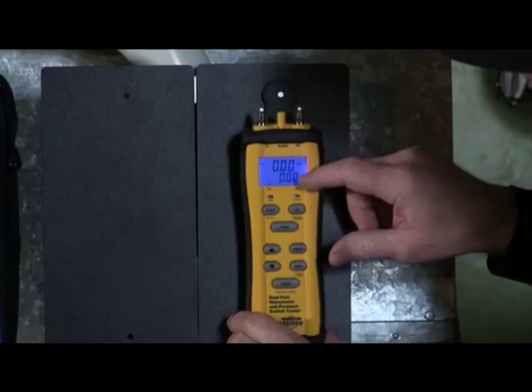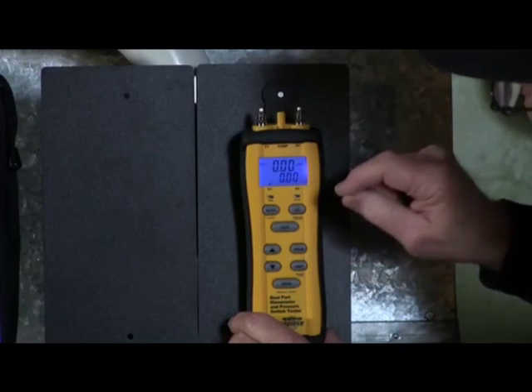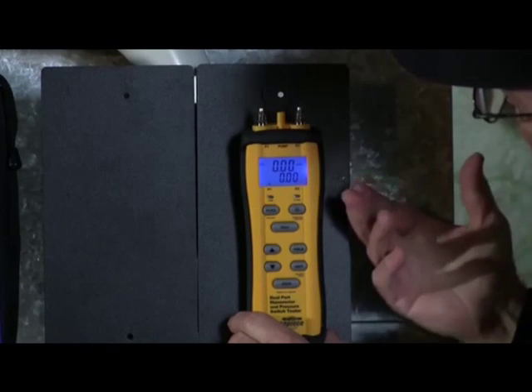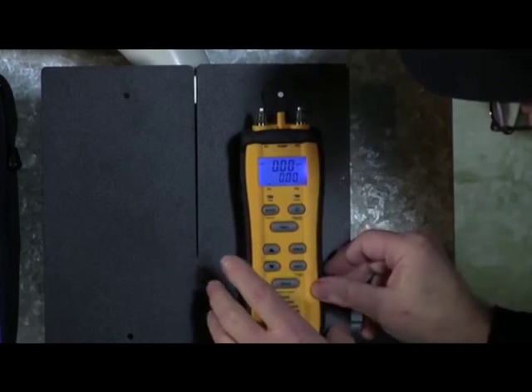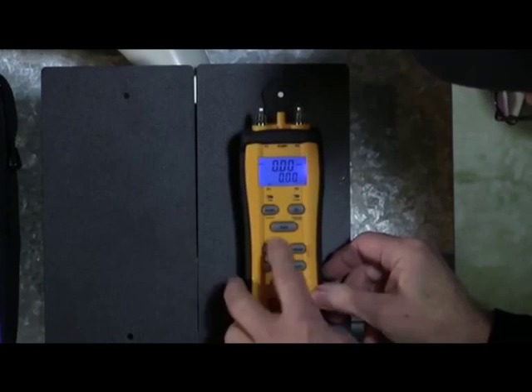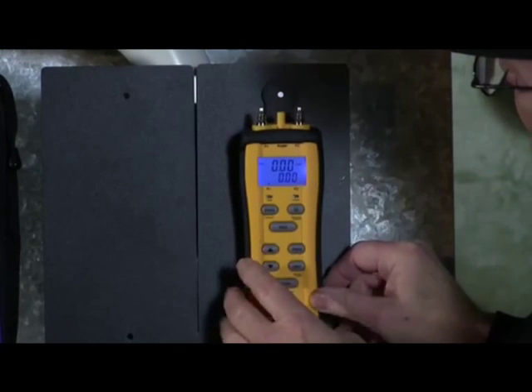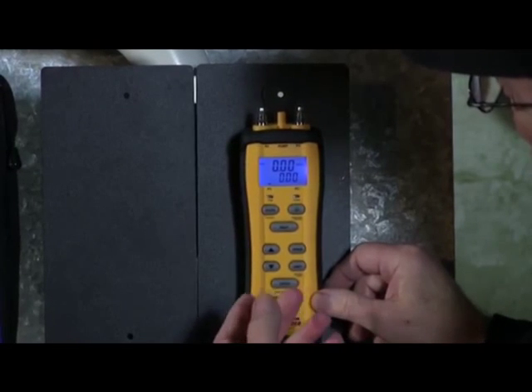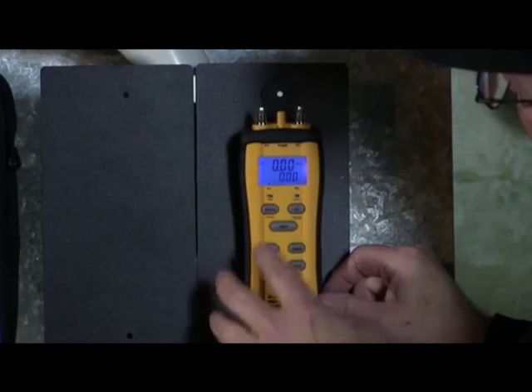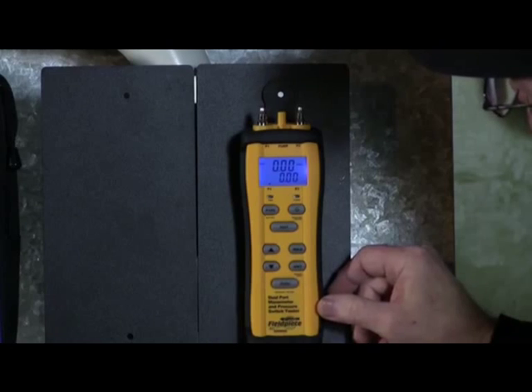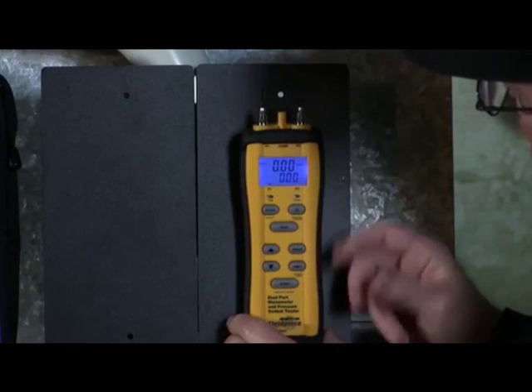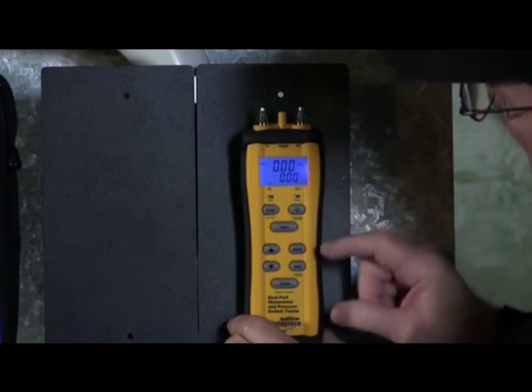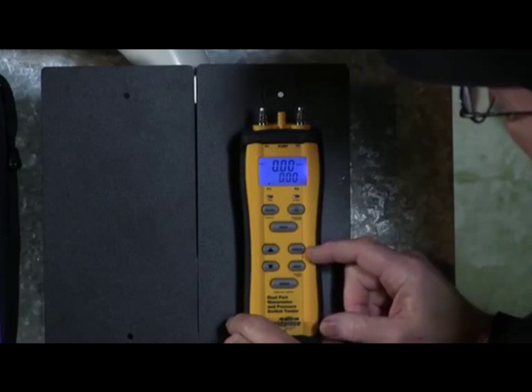The SDMN6 has a test button that turns the pump on. When you're going to perform a test on a pressure switch, you would use that button. To increase or decrease the speed of the pump, you use the up and down arrows. The hold button freezes the screen when not in test mode, and it's used to automatically capture the pressure at which it closes or opens. When you turn the pump on, you'll see the green light. When the pressure switch is closed, you'll see a red light above the word closed.